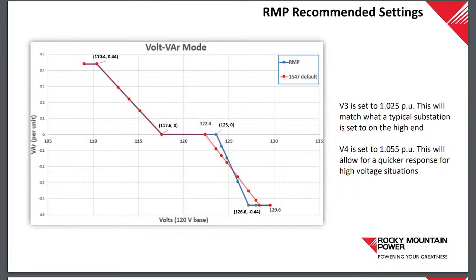As we extend out, 123.0 is going to be our first change to the default IEEE settings. So V3 goes from 1.02 to 1.025, and we put a note in there explaining why: 1.025 of 120 volts is 123 volts.